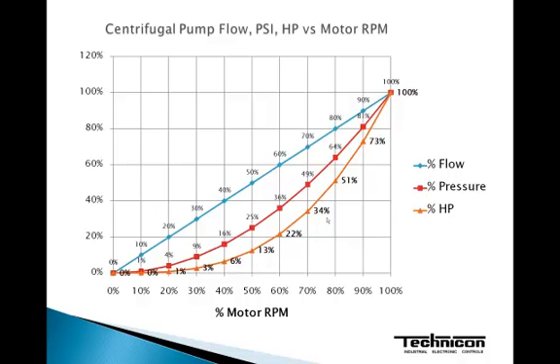Now how does that work in a practical application? This is telling us what the percentages would be. The blue line shows we have a linear rate of flow from 0 to 100%. Our red line indicates the squared function of pressure produced at the various RPMs on the X axis, expressed in percentages. And the motor horsepower is shown as a percentage of the full load. So at a 10% reduction from 100% RPM or flow, the horsepower required in that system would be 73% of the maximum horsepower.